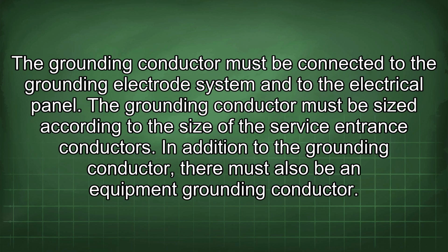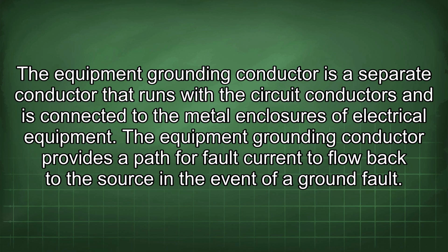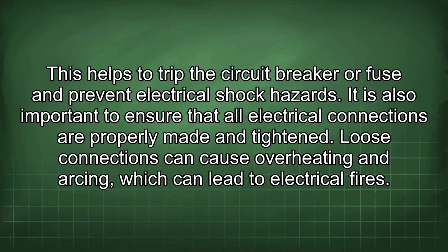In addition to the grounding conductor, there must also be an equipment grounding conductor. The equipment grounding conductor is a separate conductor that runs with the circuit conductors and is connected to the metal enclosures of electrical equipment. The equipment grounding conductor provides a path for fault current to flow back to the source in the event of a ground fault. This helps to trip the circuit breaker or fuse and prevent electrical shock hazards.